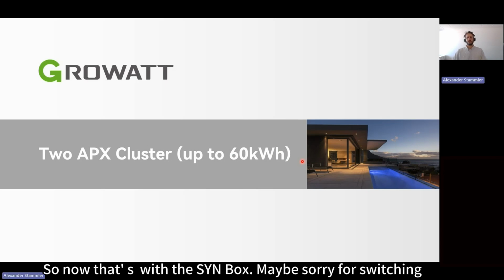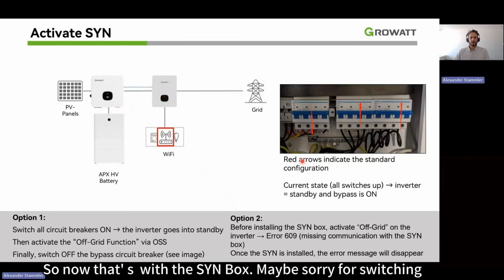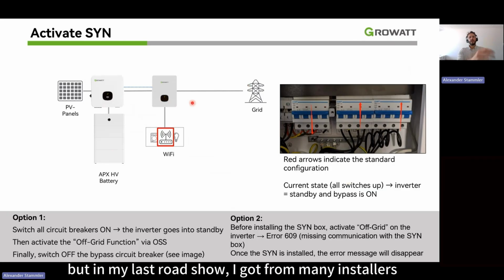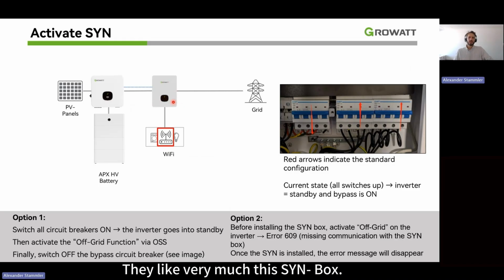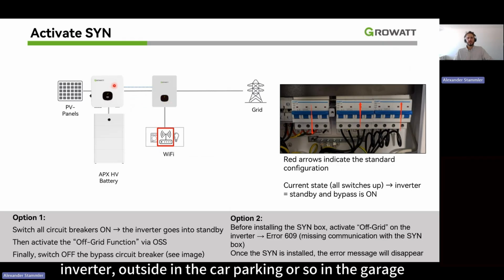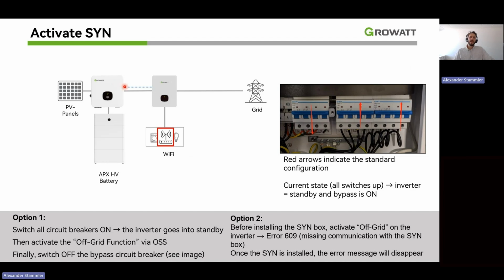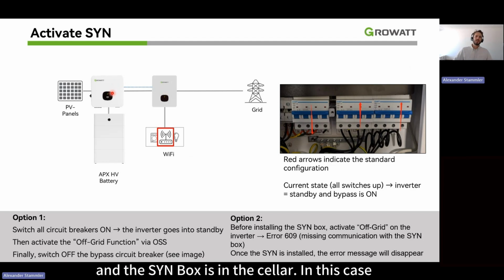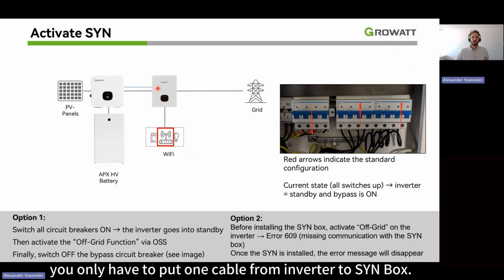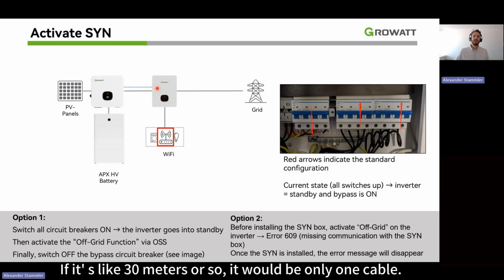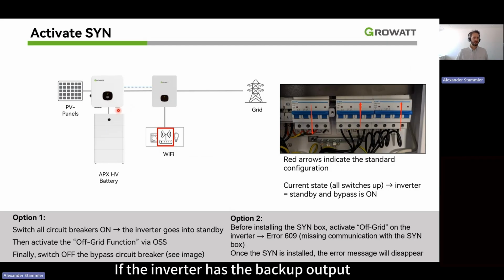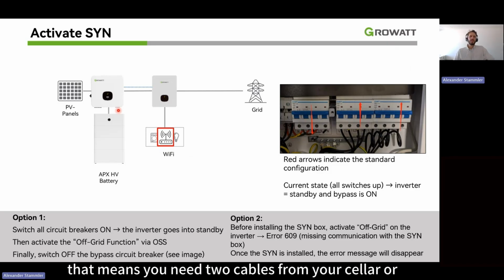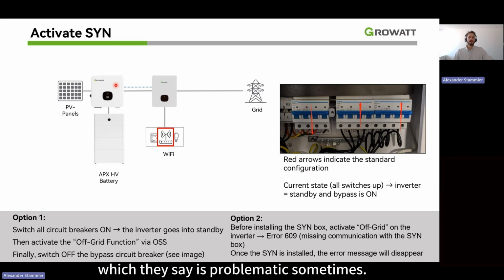So now, exactly, that's it with the SYN-box. Maybe, sorry for switching, but in my last roadshow, I heard from many installers that they like this SYN-box very much. Also because they say sometimes you have the inverter outside, in the car parking or in a garage, and the SYN-box is in the cellar. In this case, you only have to put one cable from the inverter to the SYN-box. If it's like 30 meters or so, it would be only one cable. If the inverter has the backup output, as the HU system or other systems, that means you need two cables from your cellar or where your grid access point is to the inverter, which they say is problematic sometimes.